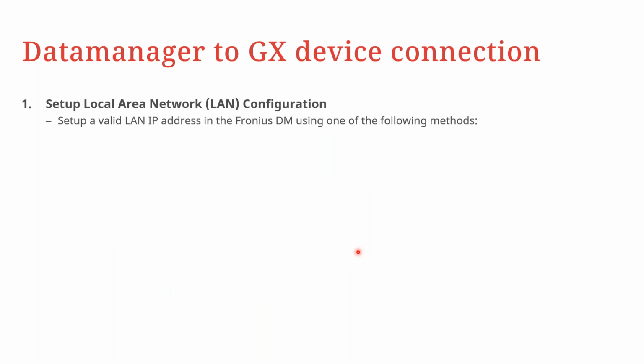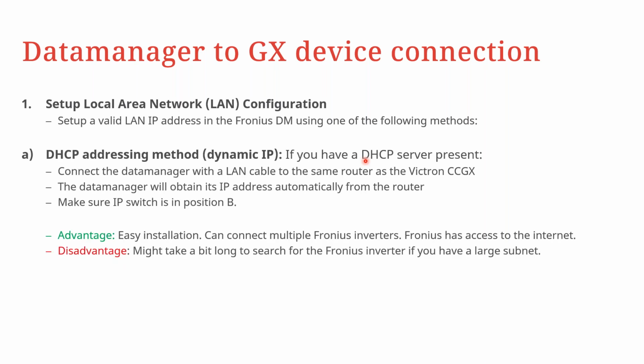So for you to establish communication between the data manager and the GX device, you have to set up a local area network configuration. What this means is that you have to set up a valid LAN IP in the Fronius data manager, and this is done using any of these methods. Method number one is DHCP addressing, or what we call dynamic IP. If you have a DHCP server, you can connect the data manager with a LAN cable to the same router as the Victron Color Control GX. In this case, the data manager is able to obtain the IP address automatically from the router. And the only thing to ensure here is that the IP switch of the data manager is in position B.